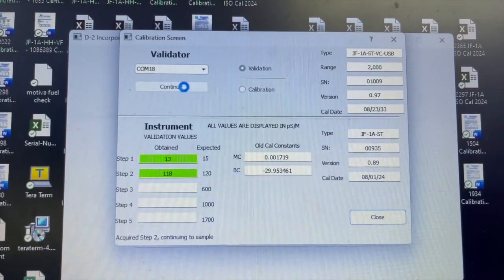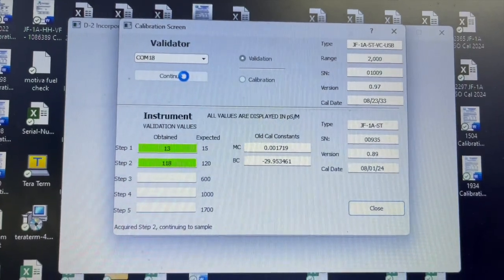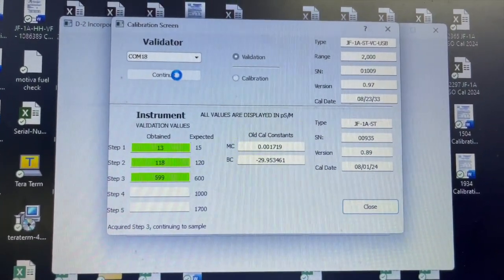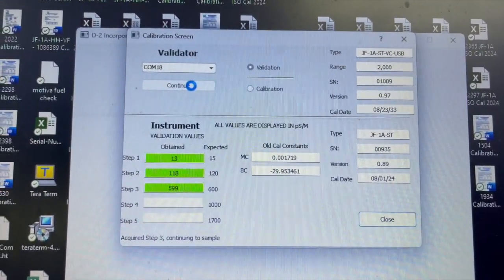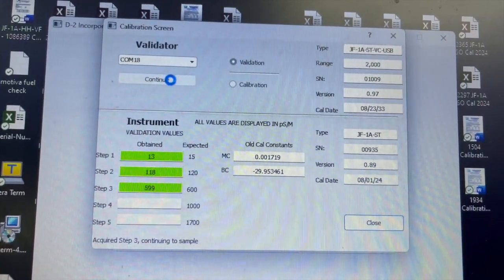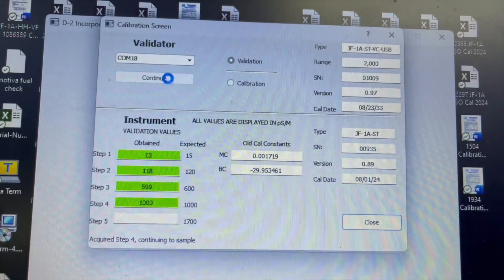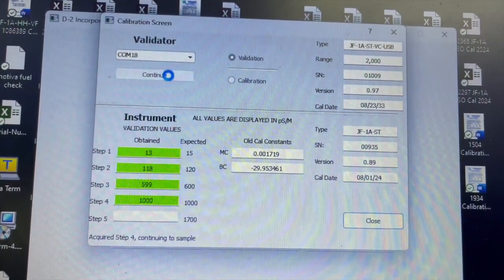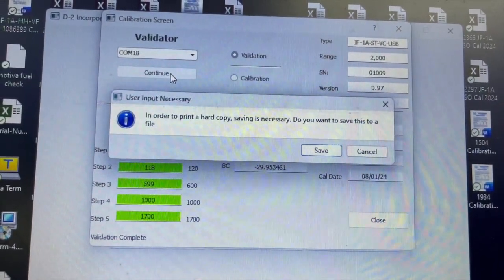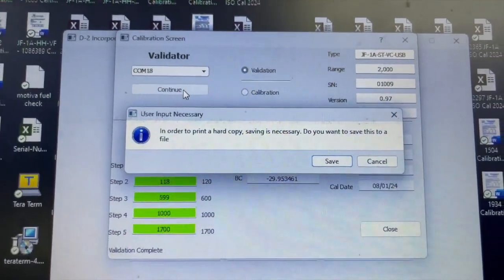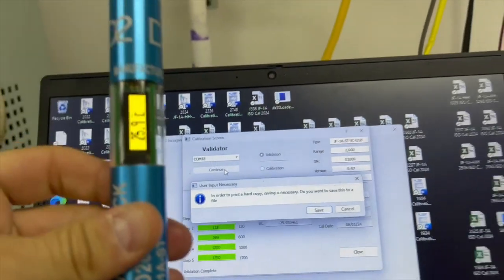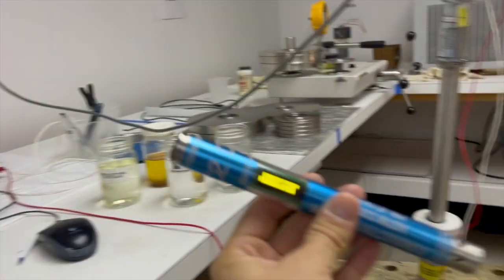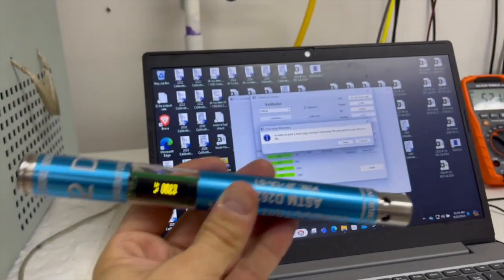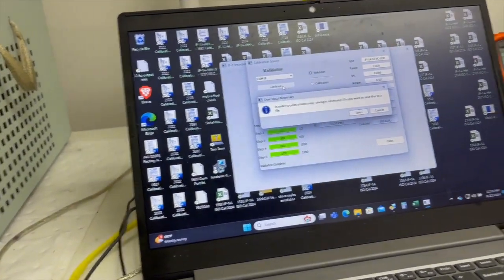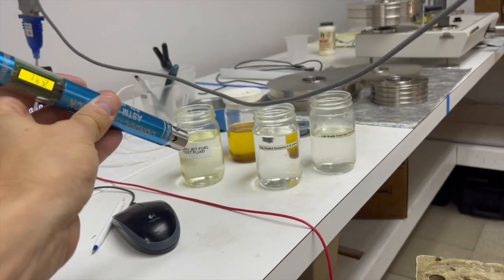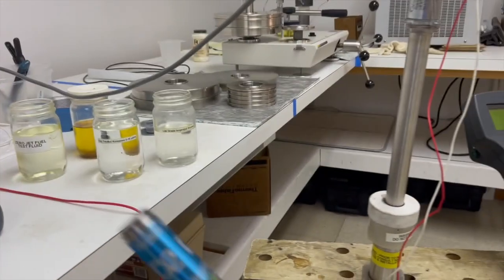You can see the data's coming out. All of these values are good, which is why it's coming out green. If it was a bad value, it would turn red. All right, and if you want, you can print a copy of this that shows this handheld was validated. And we just pull the handheld out, and now we know we can go ahead and use this handheld to calibrate that inline sensor, because this handheld is validated and verified that the calibration is right on the money. Okay, so now we can use this handheld to take measurements of these samples to know what the sample values are in order to calibrate the inline sensor.